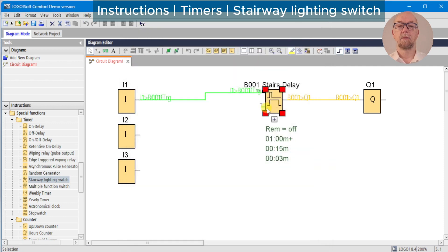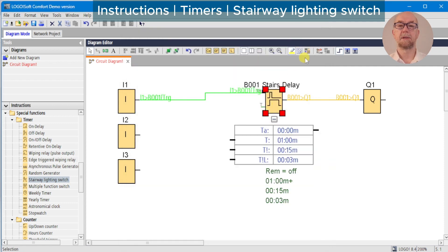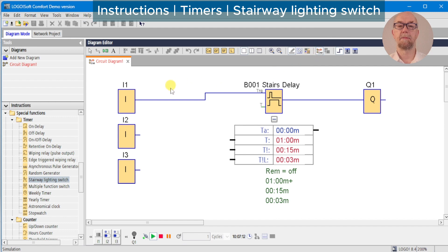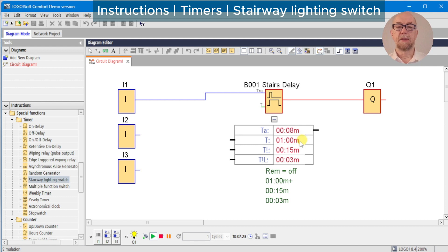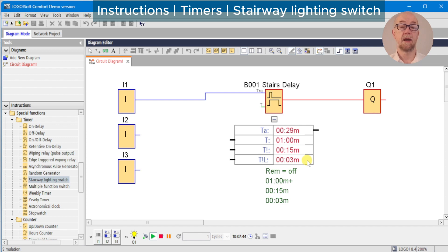We expose the timer's parameters and run the simulator. We touch and release the button and we can see the timer is now running — two seconds, three seconds, four seconds. We've set up a time delay of one minute on the lights. The 'T!' symbol is the warning time before the end of the time period — so 15 seconds before the end, the output will turn off for three seconds and then turn back on for the remainder of the time delay.